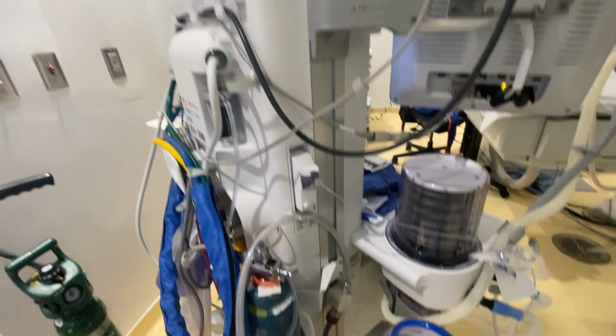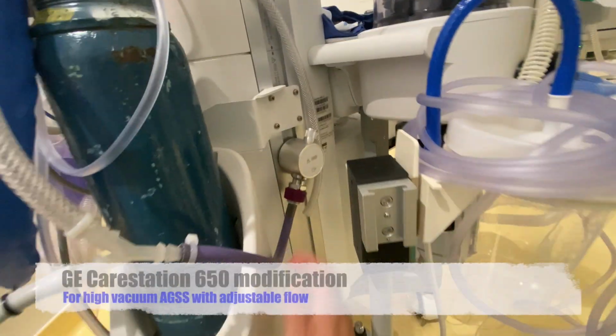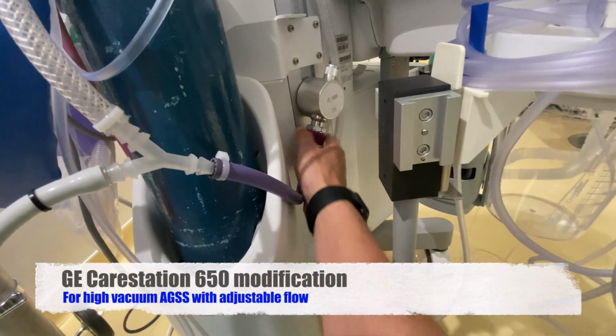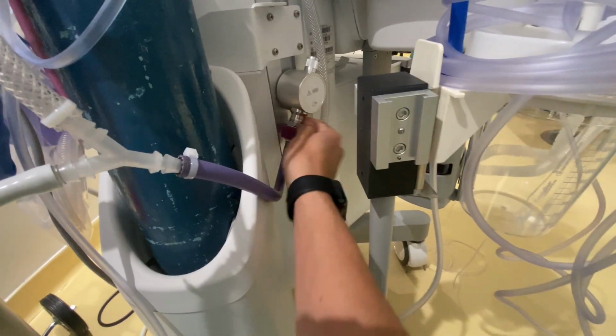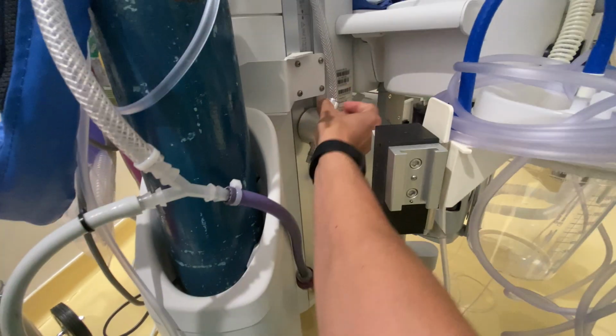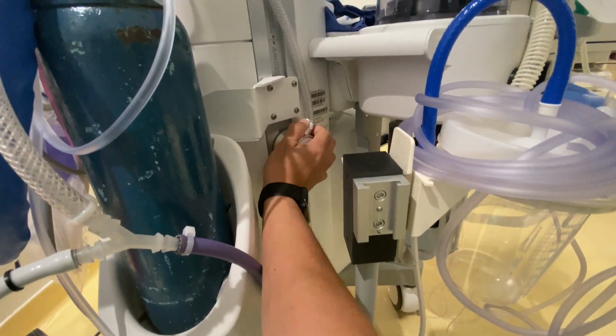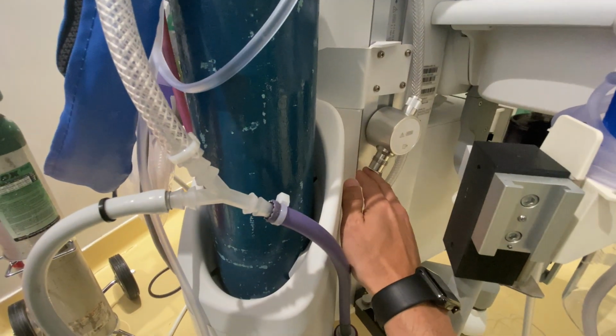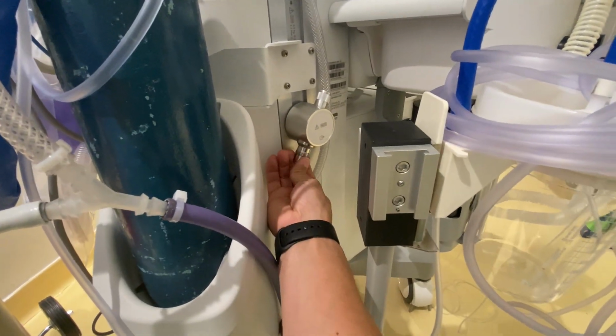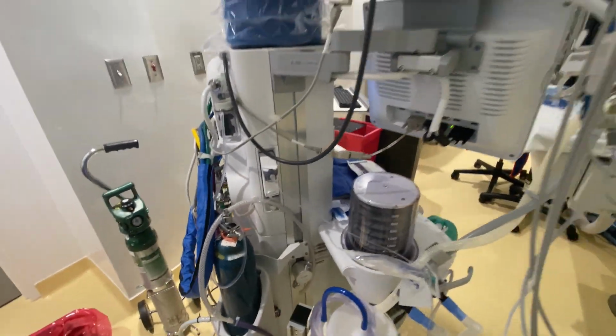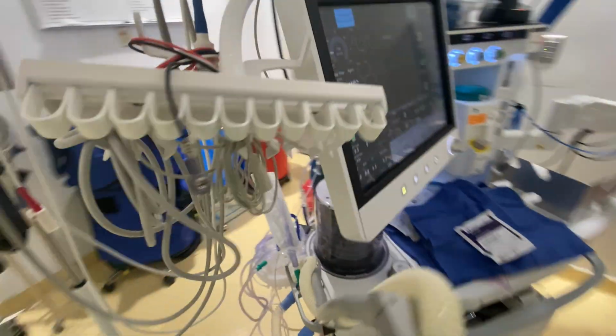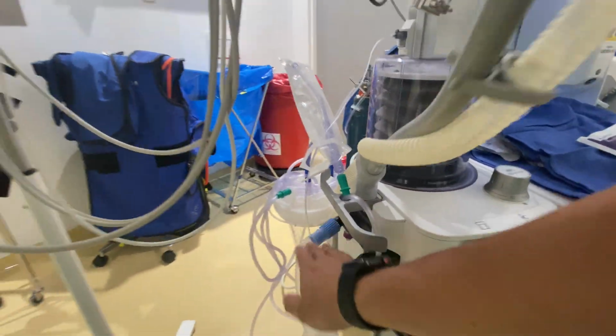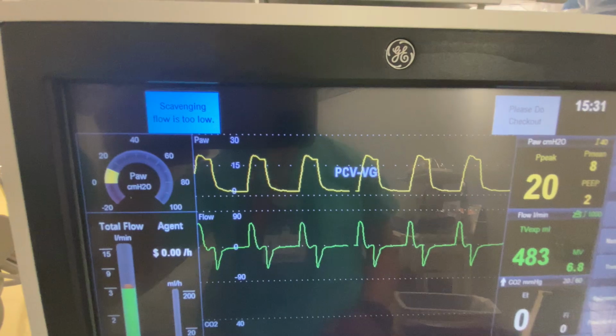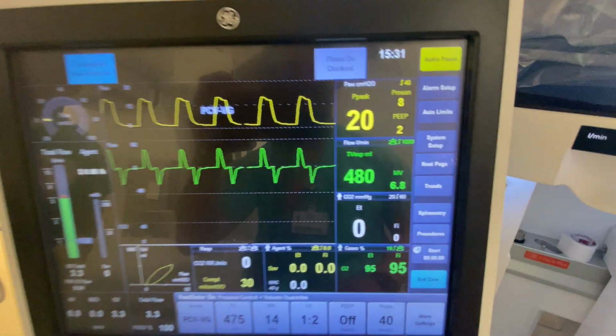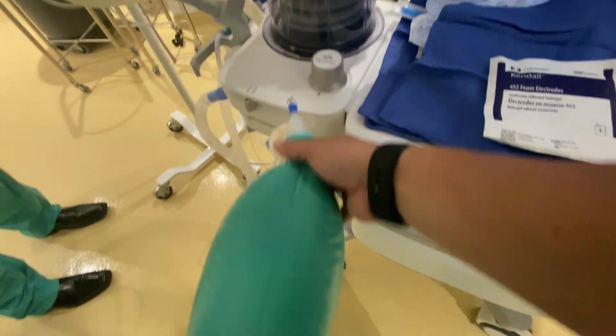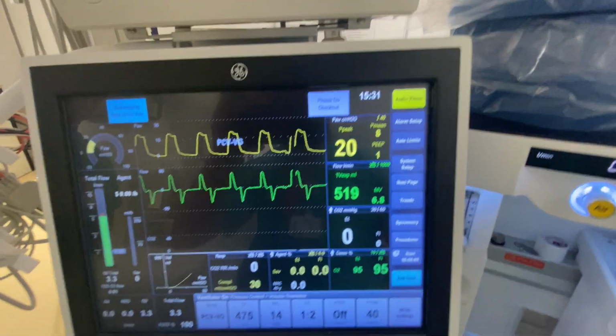Thanks. So if you find yourself in a situation where you don't have one of these fancy Y connectors to connect to suction, what happens? You'll get an alarm on the 650, but just make sure that the scavenger valve is maximally open to air. And so all of the exhaust gases from the ventilator will come out through this scavenger. So, keeping in line with our suggestions before, make sure you put a HEPA filter both at the Y and on the expiratory limb, which is this one on a GE machine. And then you'll get an alarm that says the scavenging is too low, but that's all right. You'll notice here that the PEEP is not building up in our little practice compliance lung here. Okay? All right, so that's one other option.